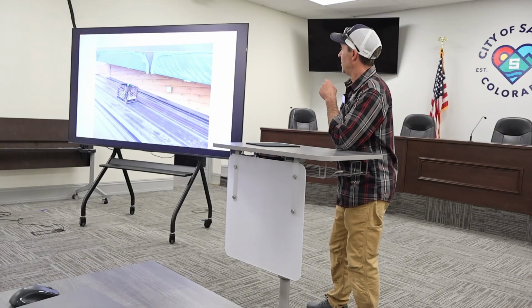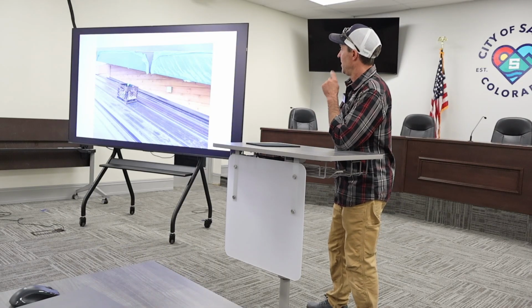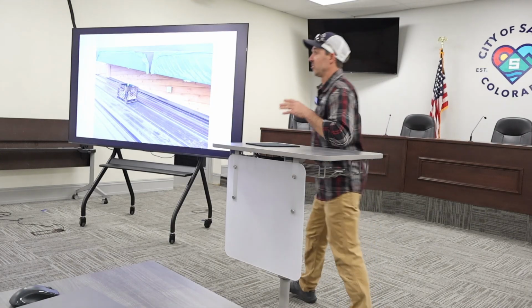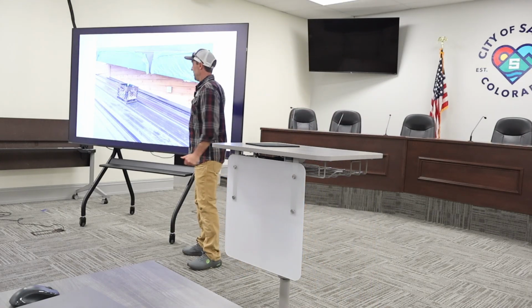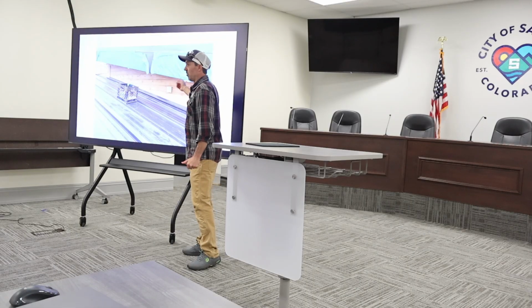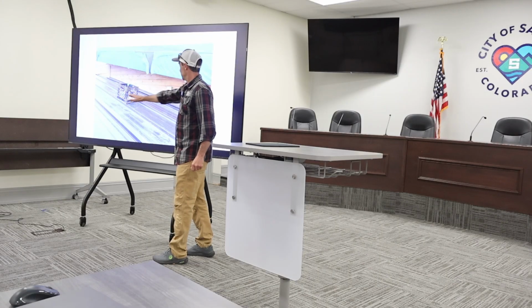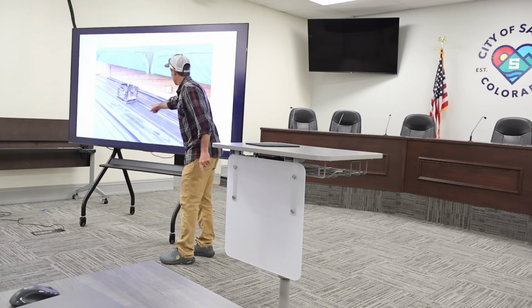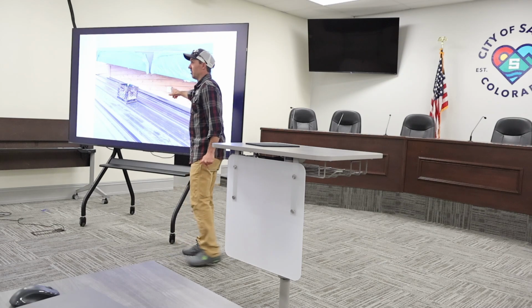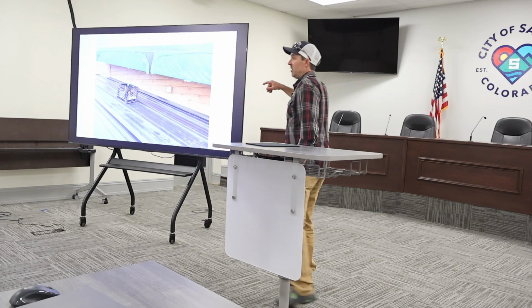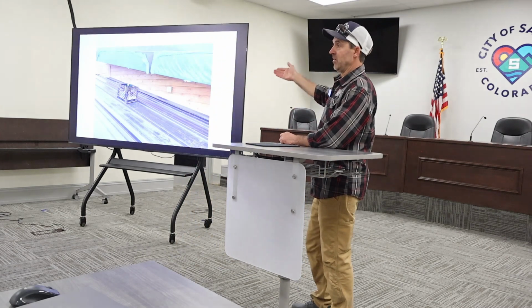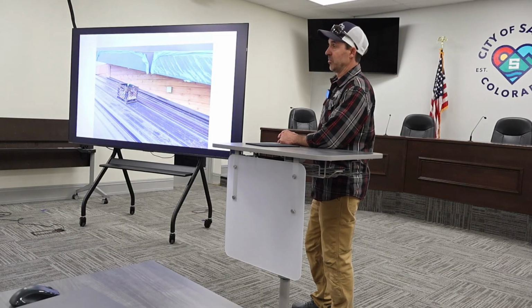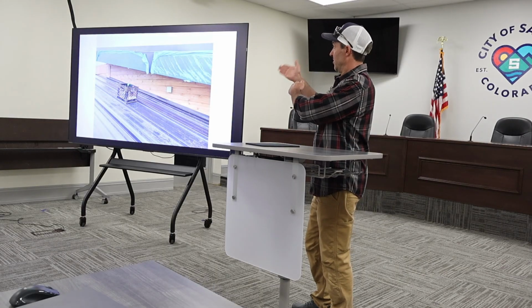This is an example of a rough-in where it's a vaulted ceiling and there's no attic space. We brought our MC cabling through the walls and put it in the bell box out here. Our solar panels ended up here. During the rough-in, we just ran a little stick conduit right up and tapped into that, so we didn't have to come down on the outside of the building. That's how we can get away with doing a rough-in without an attic space. Sometimes if you've got those kind of roof lines, it's great.